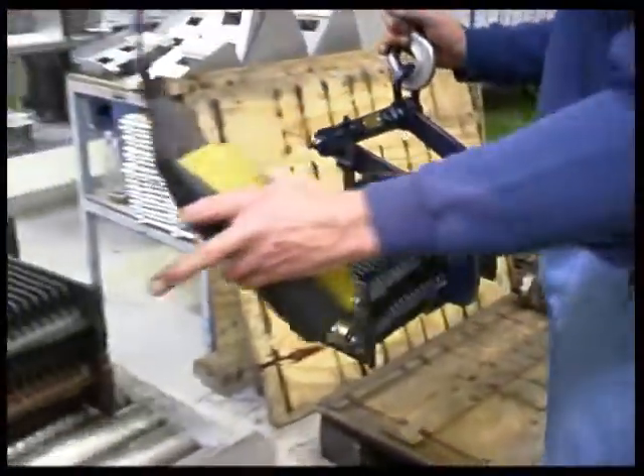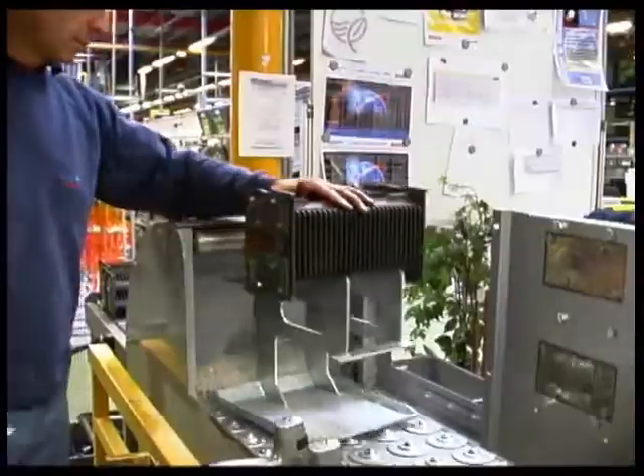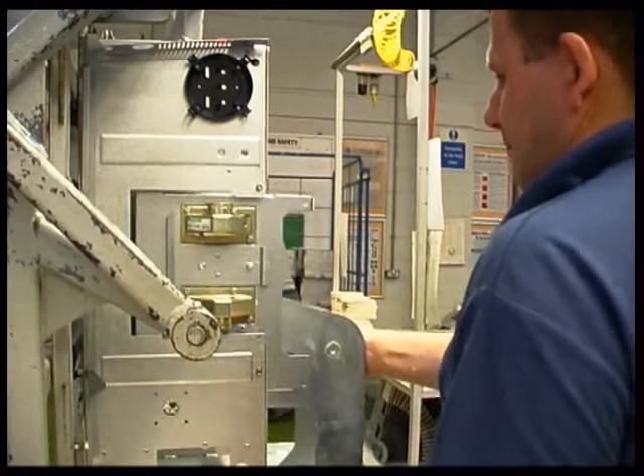At the heart of most traditional boilers is a cast iron heat exchanger. This is heated by the flames from the burner and in turn transfers its heat to the water flowing through it. The fins in the exchanger provide a large surface area to extract as much heat as possible from the flames.